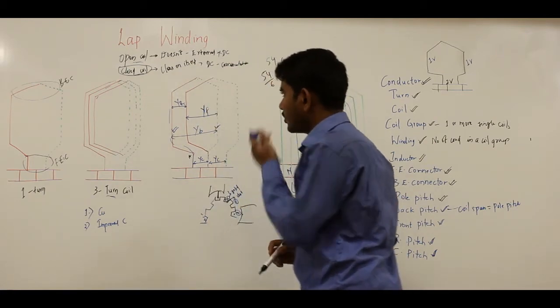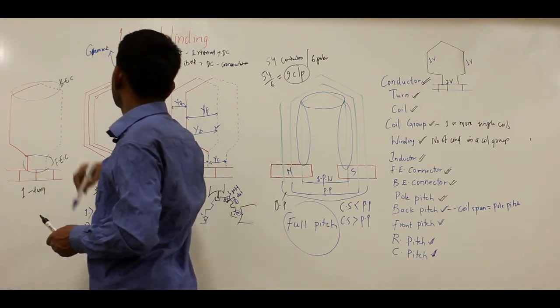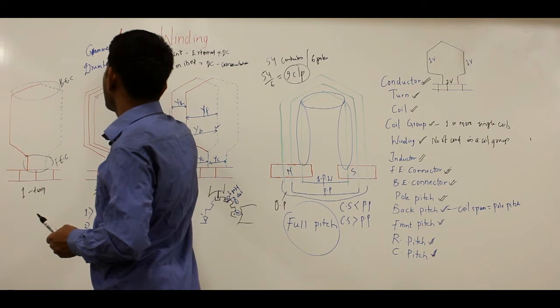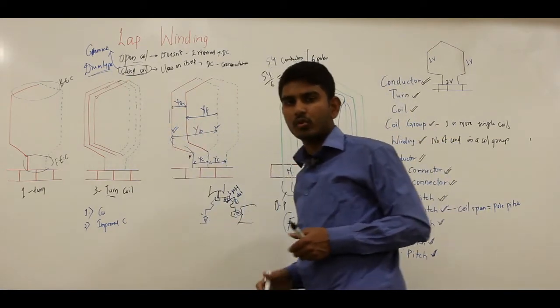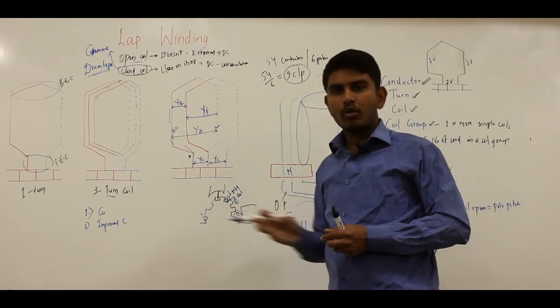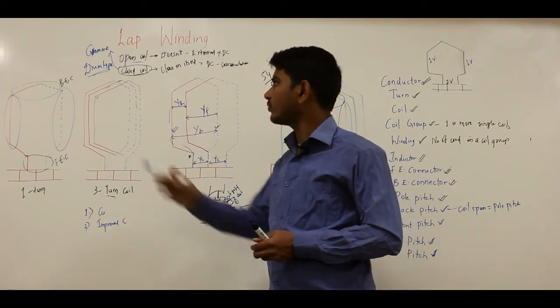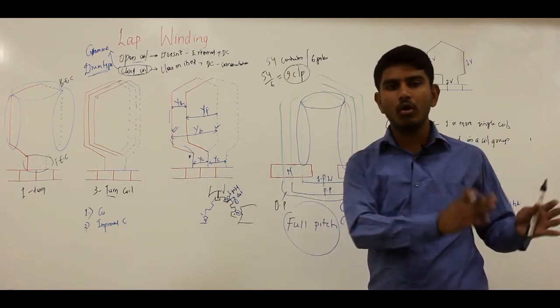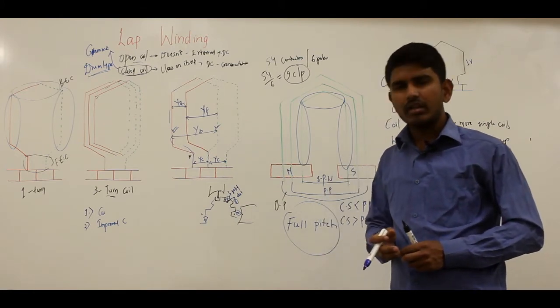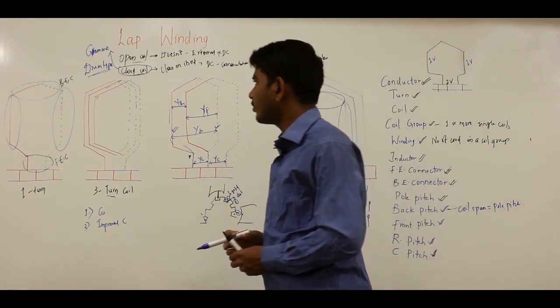Closed coil winding can be of two types: Gramme ring type and drum type winding. The Gramme ring type is an earlier winding and has been successfully replaced by the drum type. The drum type winding has two advantages: first, most of the copper conductor except the end connections is active in generating EMF; second, coils can be preformed, insulated, and then placed in the armature slots, saving labor cost.